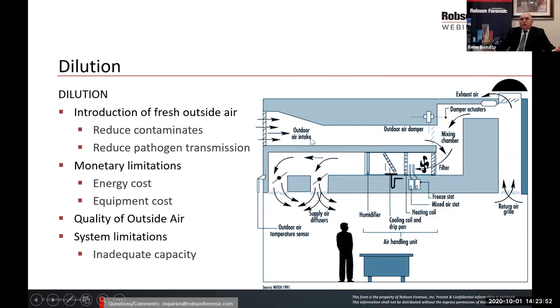There are conditions and situations, and we've designed buildings and spaces, where we have 100% outdoor air coming in. There are certain spaces that are required to do that. The first one that comes to mind is a surgical operating room. That is definitely one where you want to bring in a significant amount, if not all, outdoor air.